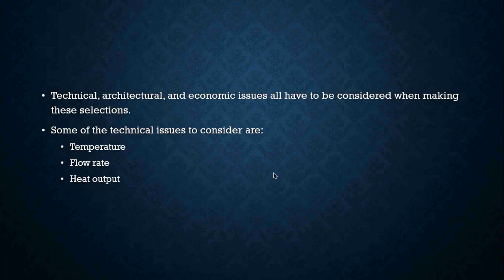Some technical issues we deal with include temperature rise we're trying to achieve. For example, with hot water or domestic hot water heating, you have to deal with flow rates. We don't want the water going too fast in the pipes because that creates noise and other issues that can be a nuisance to the homeowner. We also have to ensure the baseboards are sized correctly to put out the correct amount of heat to the space to create a comfortable environment.